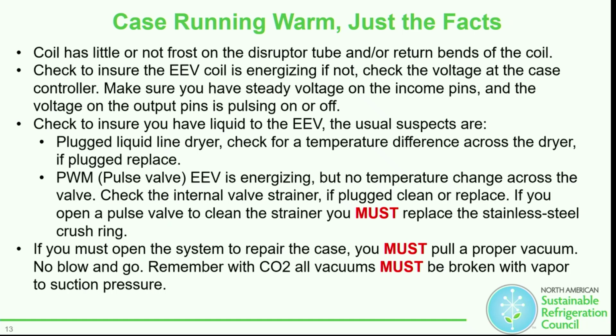Remember, with CO2, all vacuums must be broken with vapor, with suction pressure, because obviously if we put liquid in a system, because it has such a high triple point, it could potentially turn into dry ice. I know on some walk-ins, sometimes they have a suction check valve after the actual valve station. In those instances, sometimes you have to go to another case adjacent, run a 100-foot hose to get vapor over in order to break that vacuum, because they have a check valve. A lot of walk-in freezers do, if you're not aware.